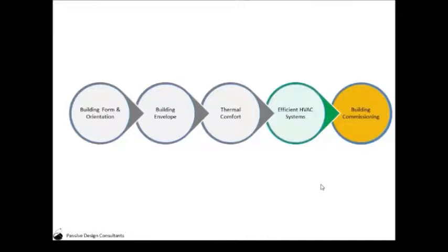Ultimately, when the project is built, when the systems are installed, the project should also do building commissioning. Building commissioning means checking all these factors properly throughout the building design, construction, implementation, and installation process, and checking whether all these systems installed in the building are working properly to provide thermal comfort, are designed properly to address heat gain from the building envelope, and meet the right comfort for the occupants and achieve their energy efficiency as well.